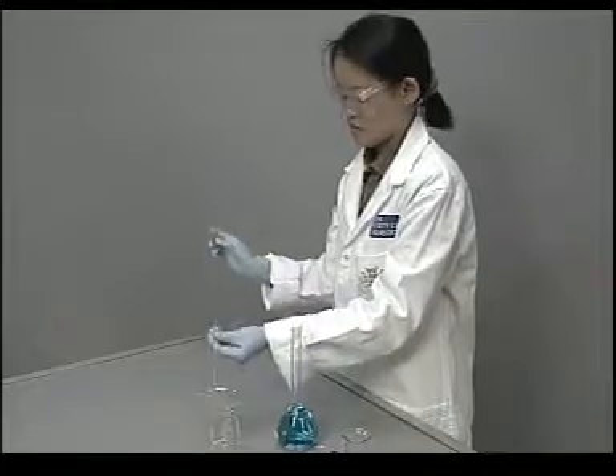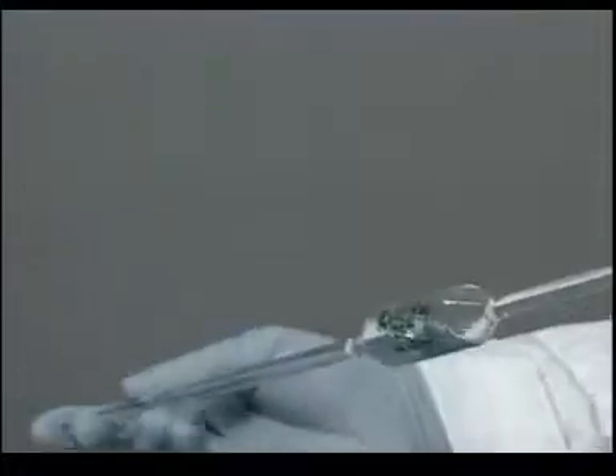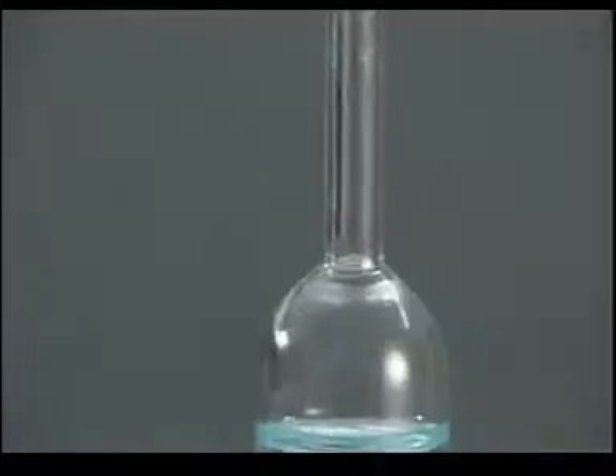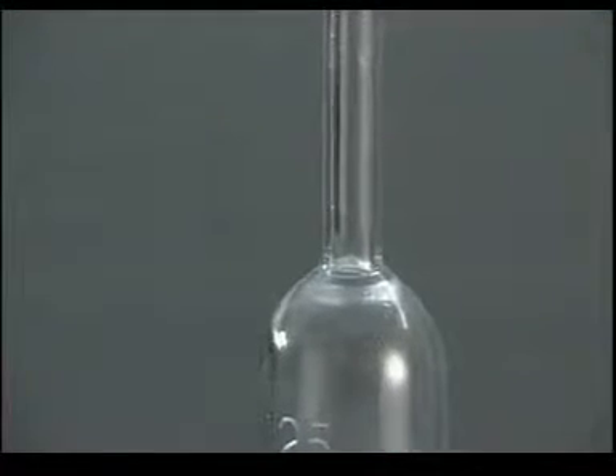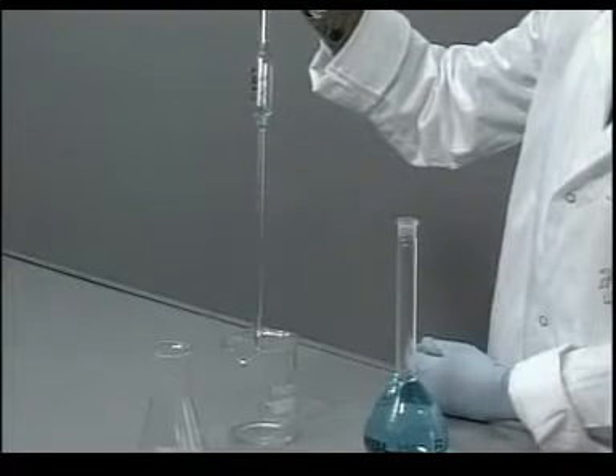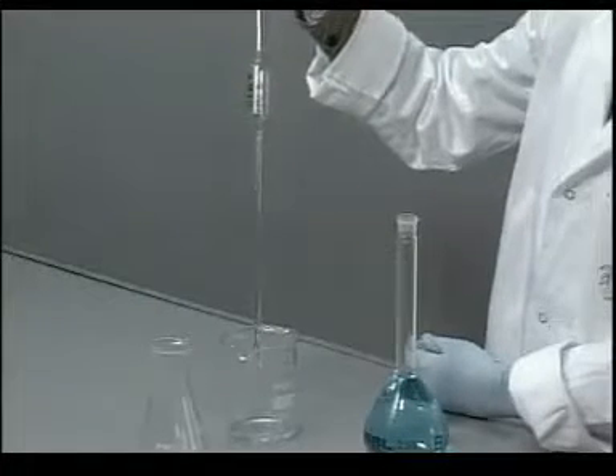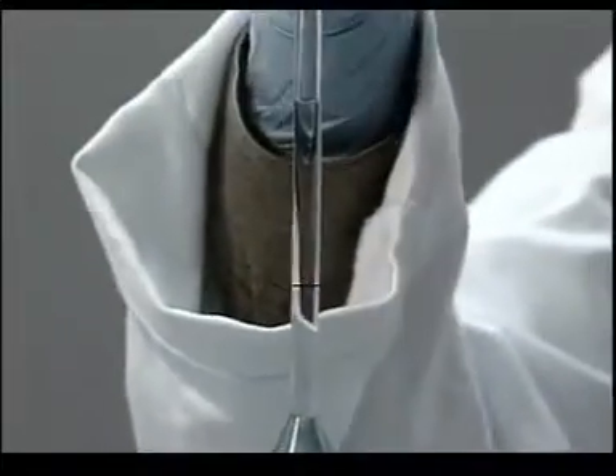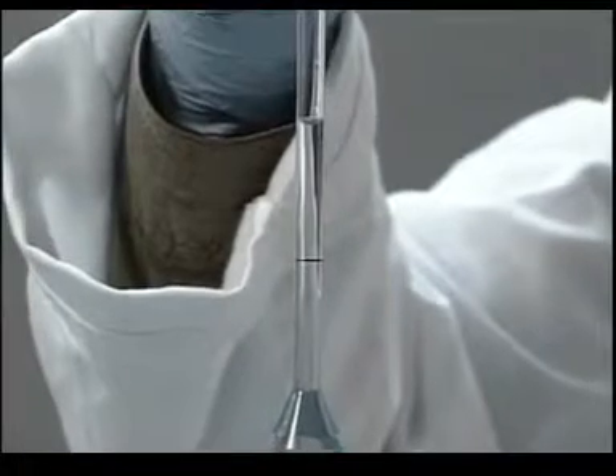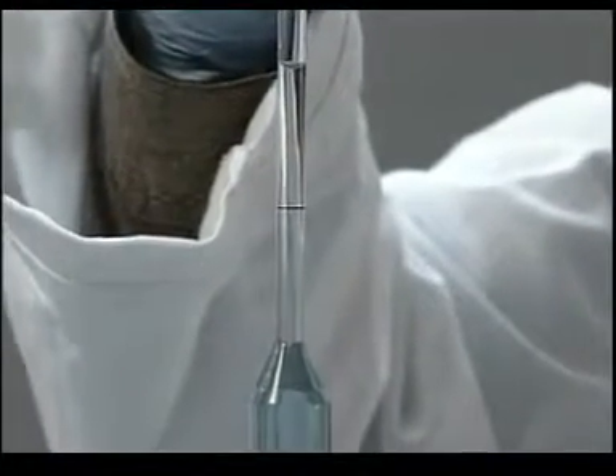Rinse the pipette out twice with the solution that is to be measured out. If the solution does not cover the sides of the pipette evenly, the pipette is dirty and should be cleaned with a cleaning solution and then rinsed with water. The solution from the two rinses should be run into a beaker and discarded. After rinsing, draw the solution into the pipette until it is about 3 centimetres above the calibration mark.